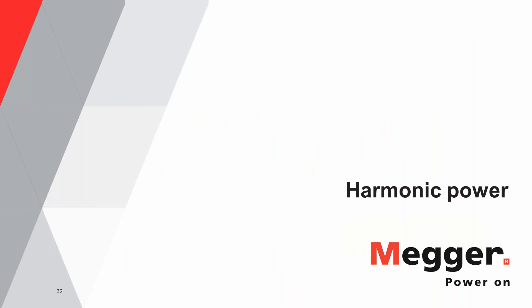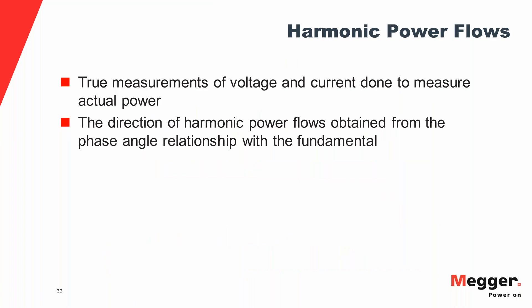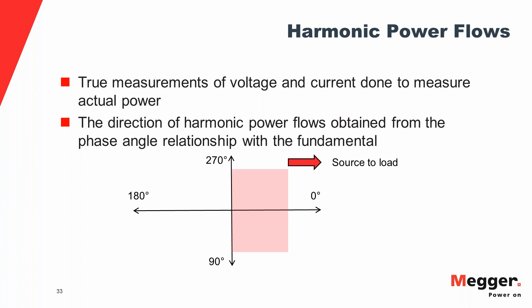The next section is on harmonic powers. Power is measured using true RMS values of voltage and current. For individual harmonic powers, the direction of flow differs from harmonic to harmonic — it's not the same as for fundamental power. The direction of power flow is determined by the phase relationship of the harmonics with the fundamental. If the phase angle difference lies between 90° and 270°, the direction is from source to load. If the phase angle difference falls in the negative quadrant, the direction is from load to source.